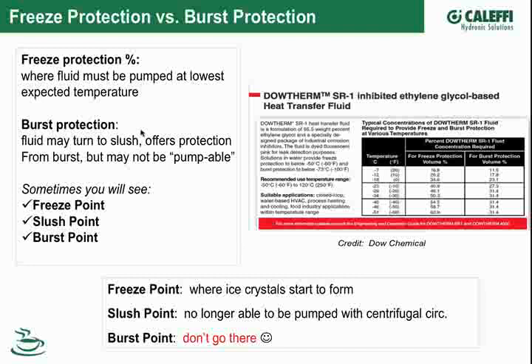Burst protection means you've got enough glycol in there to prevent too much ice from forming, and to prevent the ice from agglomerating and bridging across tubing in a way that causes rupture. So at the end of the day, freeze protection is the safer way—if your freeze point is lower than the coldest anticipated temperature, you'll have no chance of rupturing your equipment because ice will never form. With burst protection you can get away with a little less glycol, but you have to make sure your fluid can still flow to relieve pressure as ice crystals form. We talk about that more in our literature.